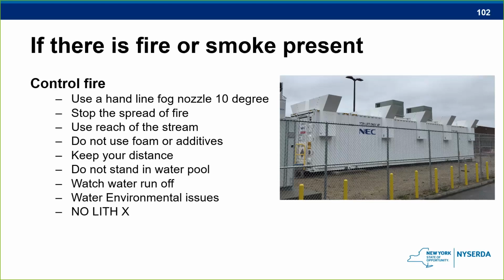If you are putting water directly onto an energy storage cabinet, just be concerned about the potential of electrical leakage back to the person on the nozzle itself. That's why we tell you to use a 10-degree fog nozzle, to limit the amount of energy coming back. We also tell you to stay 10 feet back if you're concerned about that. I want you to be back even further than 10 feet. Really use the reach of the hose line itself and have your forces stay back.